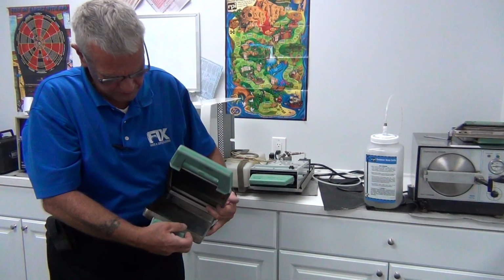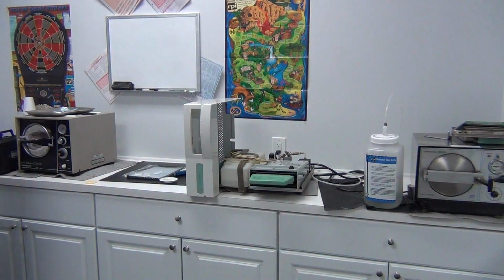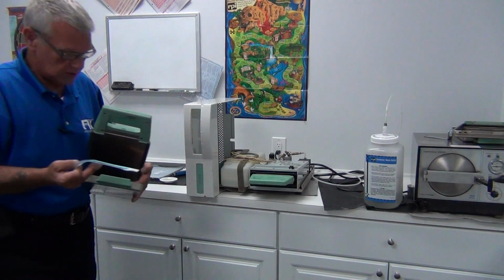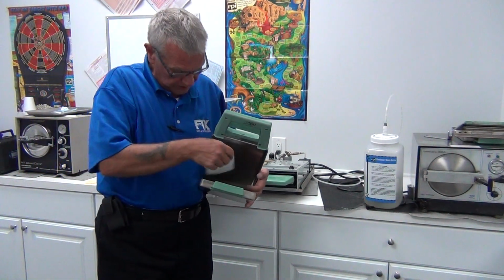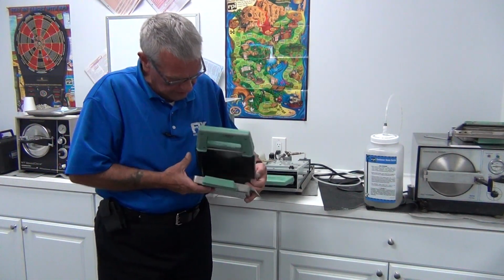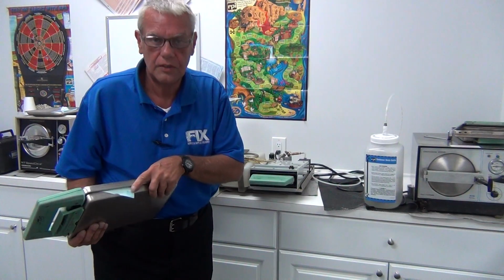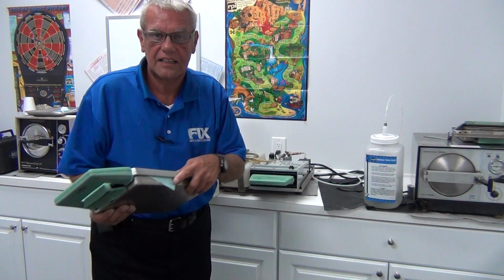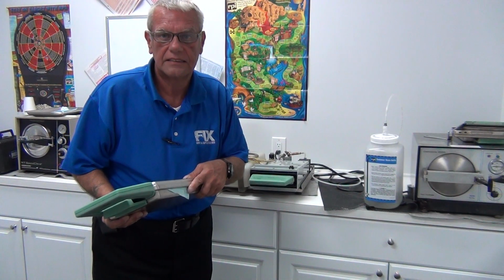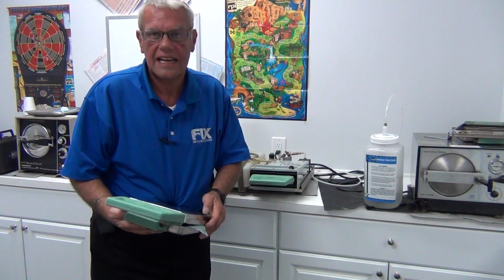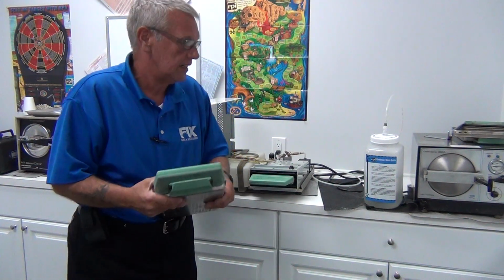Very important not to do this when they're putting sterilized instruments in there. This is going to be one of your common problems too. See that? That gasket can only take so much of that. Everything needs to be contained inside the cassette.